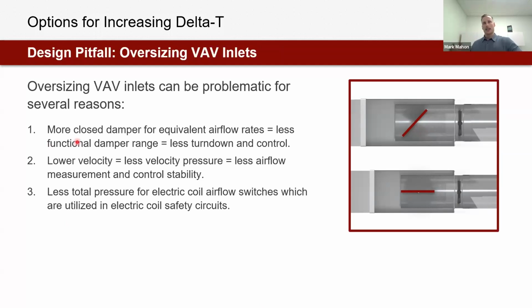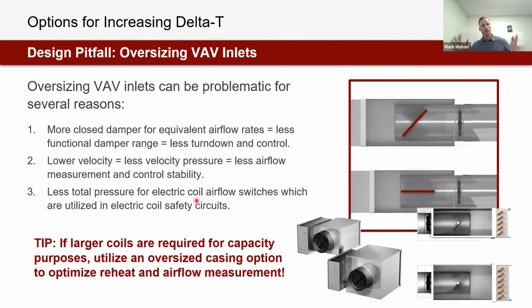The reality is, if we make the inlet bigger, it just means the damper is going to have to be more shut. So a more closed damper means we have less functional damper range, less movement to that damper, which means we're going to have less turn down and control. Lower velocity means lower velocity pressure, which means potentially less airflow measurement and control stability. That can also be a problem for electric coils, which we've been discussing in the chat in some context here as well. So if we need more capacity, if we want a larger delta T, let's not oversize the VAV box. Let's actually use an oversized casing instead.